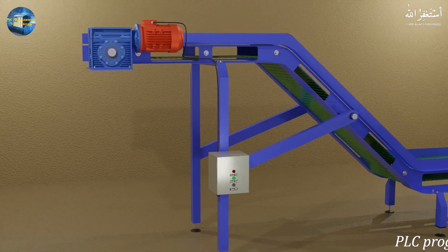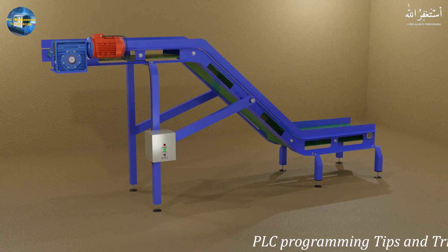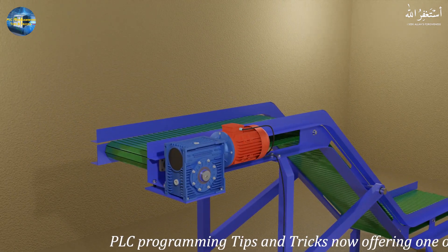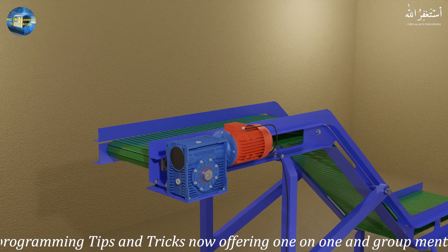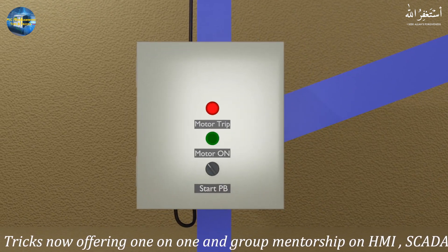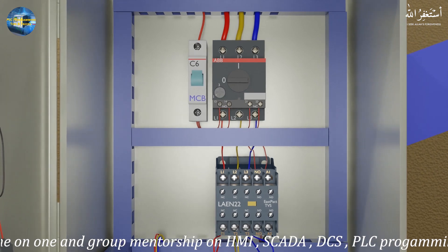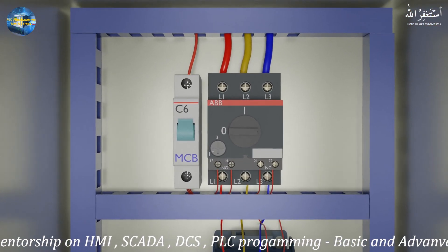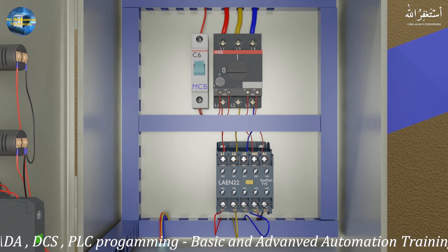After some time, the conveyor motor starts to overload and draws more than the rated current, and eventually the motor protector breaker inside the control panel trips and the conveyor stops. If we go back and open the electric panel for this motor, you can see that the motor protector is tripped, cutting the power being supplied to the motor by turning off its contactor. Now the motor is tripped.